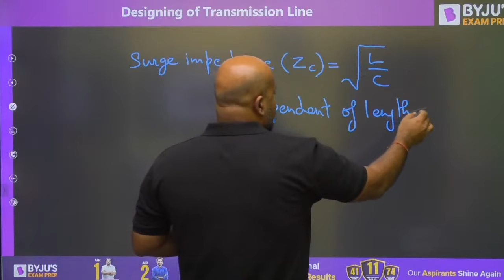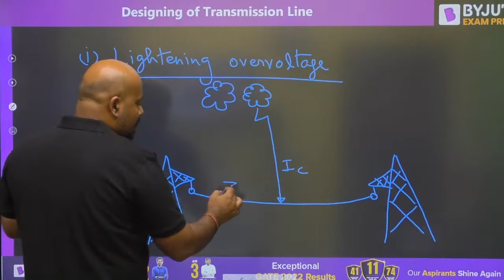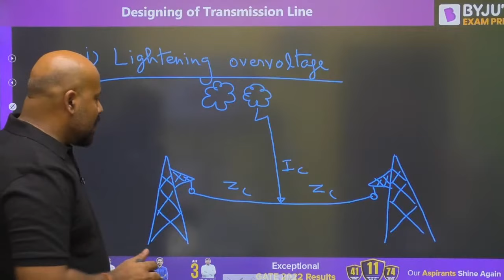So when the surge impedance is independent of the length of the line, it means it is immaterial at what point this discharge happens. The impedance seen by this discharge current is going to be the same on both sides. So by using this path, this lightning discharge current goes to the ground.